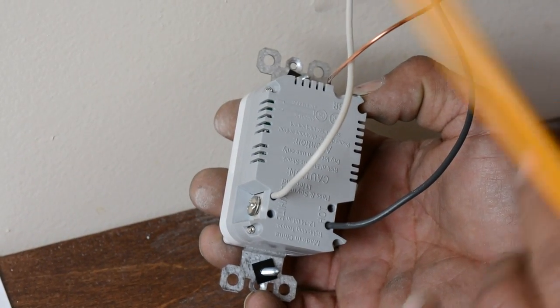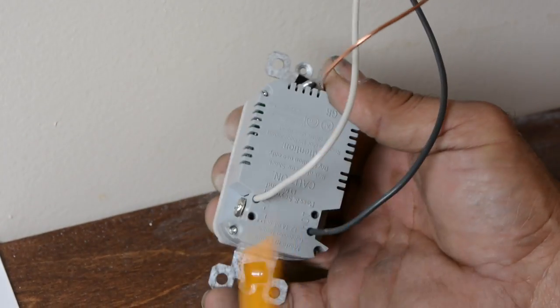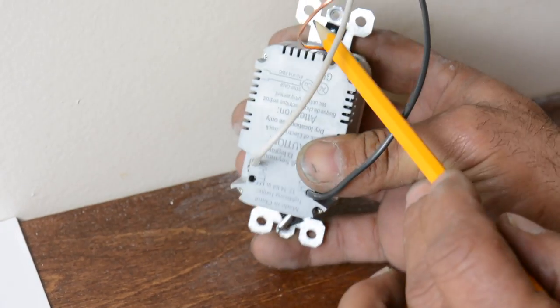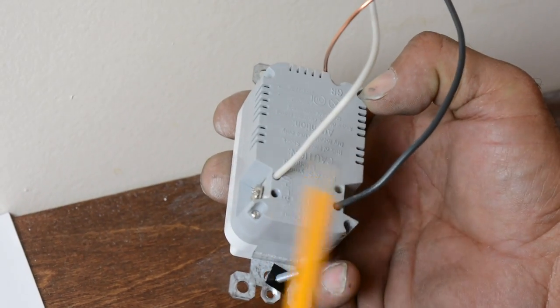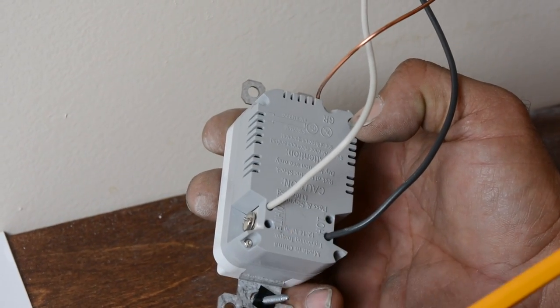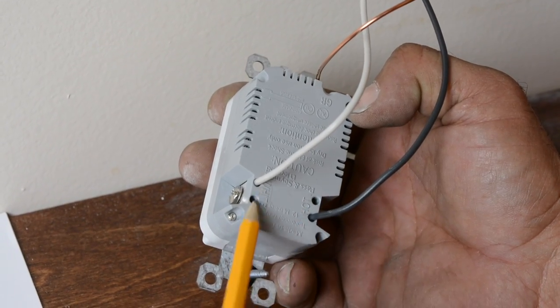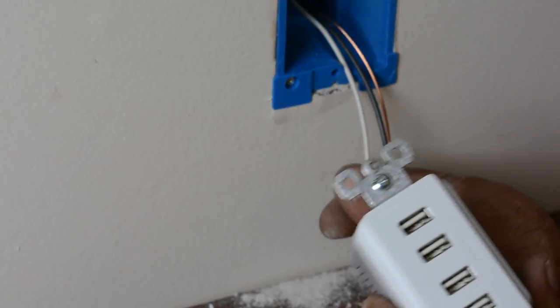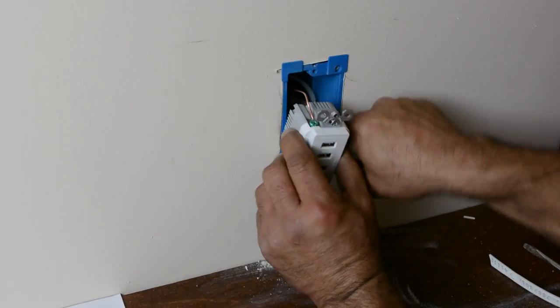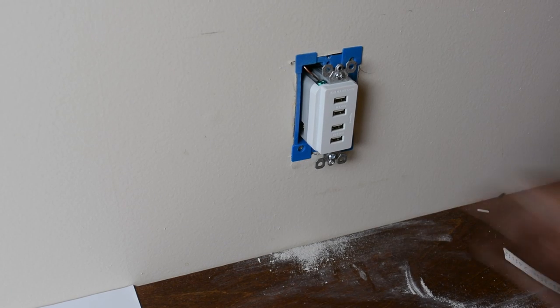Our outlet is now connected to our wire that we installed. If you were just replacing an outlet with one of these USB chargers, you can see it's marked white — neutral — and the other one is marked hot, which is black. Then you have your ground. If you only had two wires, then it's a simple remove and replace. But if you had four wires going to another outlet, that's where you'd connect those — power in, power out. We're going to coil these wires and push them back in the box, making sure they're in nicely. Now we can secure our outlet, then turn the power on and test it.